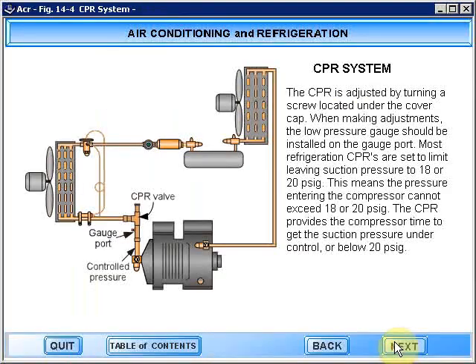The CPR is adjusted by turning a screw located under the cover cap. When making adjustments, the low-pressure gauge should be installed on the gauge port. Most refrigeration CPRs are set to limit the leaving suction pressure to 18 or 20 pounds gauge. This means the pressure entering the compressor cannot exceed 18 or 20 pounds. The CPR provides the compressor time to get the suction pressure under control, or below 20 pounds.